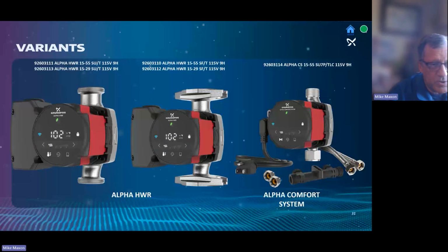So I said we have two products, but we have 5 part numbers because the HWR will come in the union, same union that we've always used on the Alpha and the UPS, and a stainless flange. I said same union, but these are different housings. These are optimal hydraulic performance. You can't take this pump head and put it on a UPS pump housing. It must use this pump housing. But they are in 1529 as well as 1555 on the HWR products. Then we have the Alpha Comfort System, which uses the same valve that we're using today, the new XL valve. Same valve. And so you see it has the line cord and no numeric display.